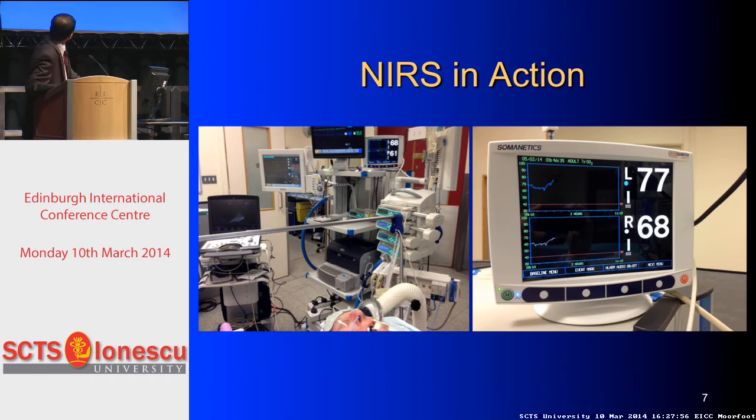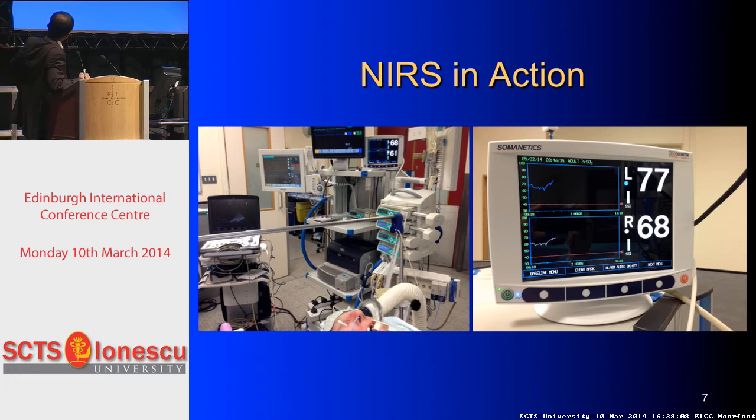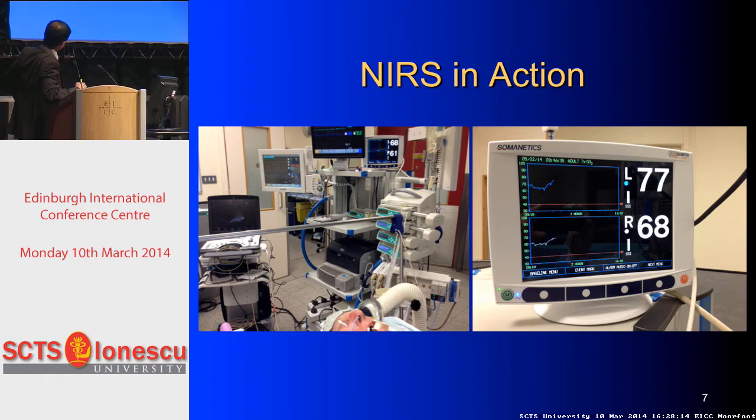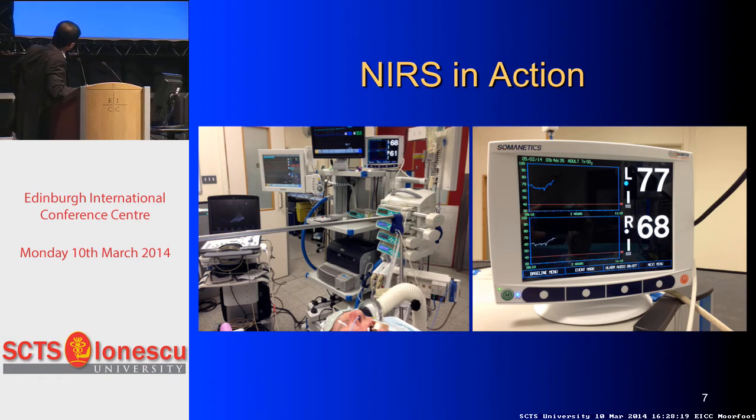So here you can see our setup for cerebral near infrared spectroscopy in our theaters. You can see the patient's head with the two sensors applied, and that's the INVOS monitor, the near infrared spectroscopy monitor. It's quite a compact and portable screen, which can be placed next to the main monitor so everyone can see it, including the surgeon and the perfusionist. And those are the normal values. You can also appreciate that you have two channels for the right and the left side, which are separately monitored. And you also get a display of the trend, which is monitored all the way through.